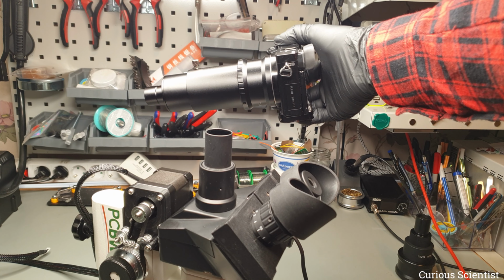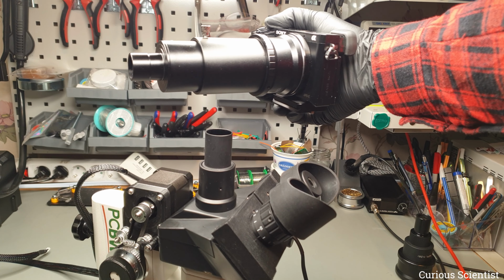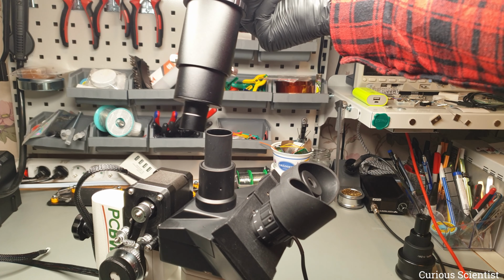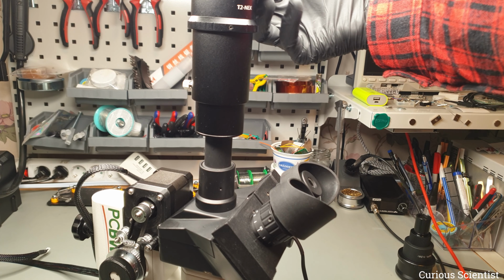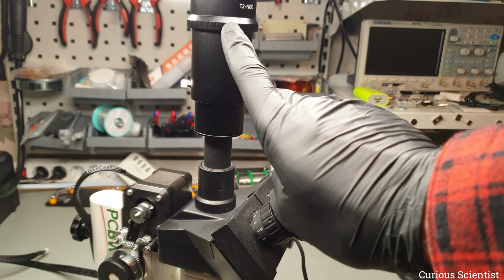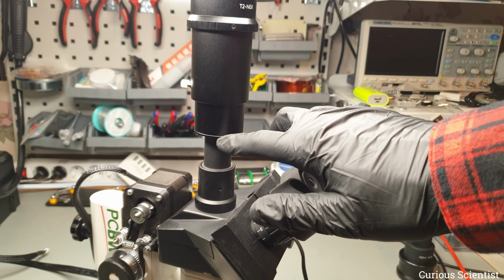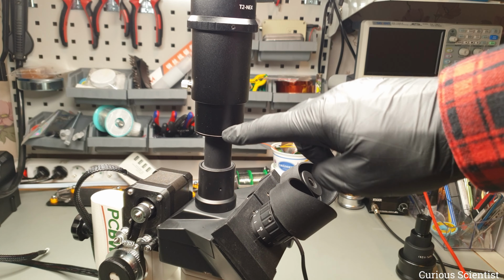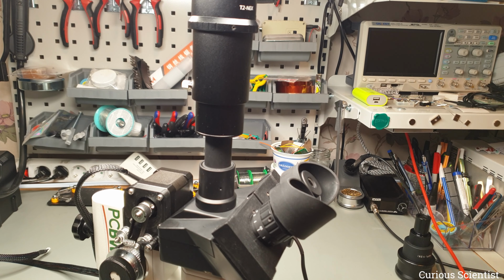So here's the big boy tube. It's quite long, as you can see. This will go on the camera. And you cannot even see the camera up there because the distance is so large. And actually this is totally retracted, so this inner tube is hitting the surface here, so I cannot make it shorter. But it's not a problem, and you will see exactly what the camera sees now. So let's switch to the camera. Right now, this is what the camera sees, and I haven't changed the focus. So the focus is still at the same setup as I left it with the optical element. So I will have to change this now.